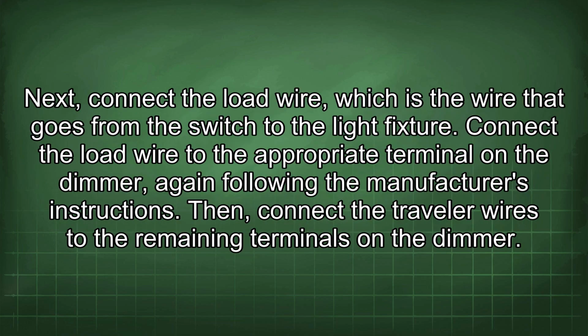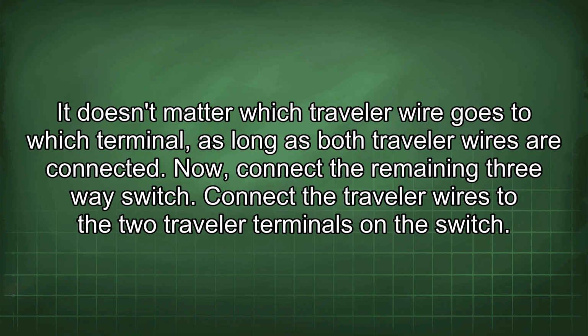Next, connect the load wire, which is the wire that goes from the switch to the light fixture. Connect the load wire to the appropriate terminal on the dimmer, again following the manufacturer's instructions. Then connect the traveler wires to the remaining terminals on the dimmer. It doesn't matter which traveler wire goes to which terminal, as long as both traveler wires are connected.